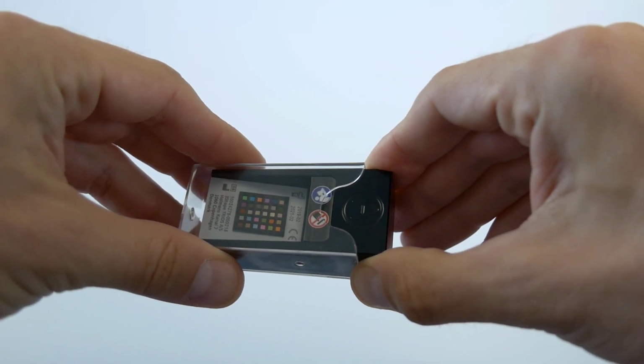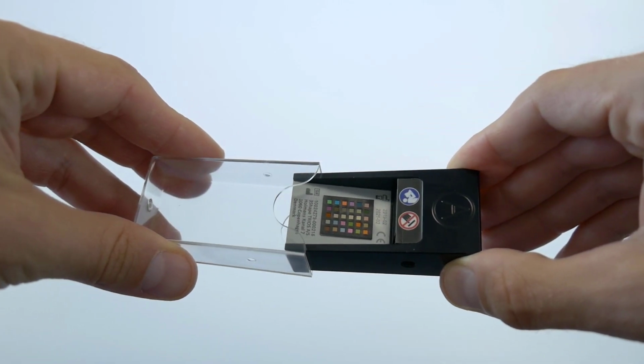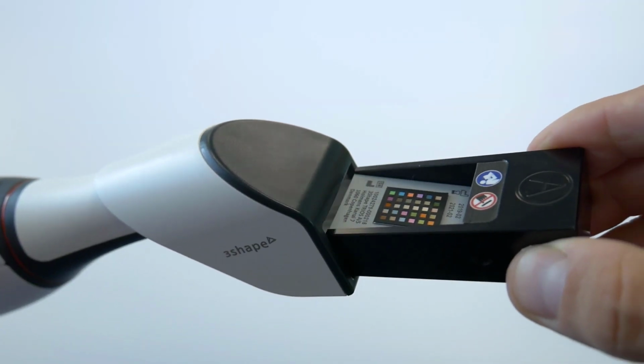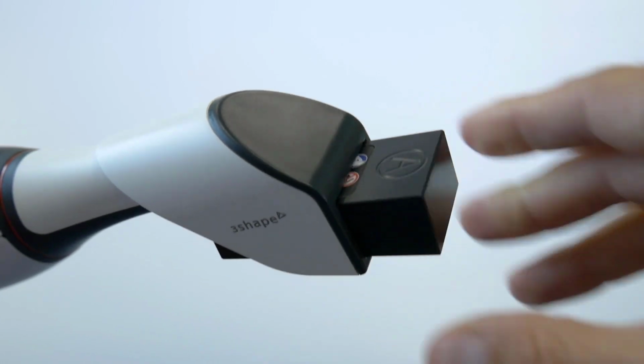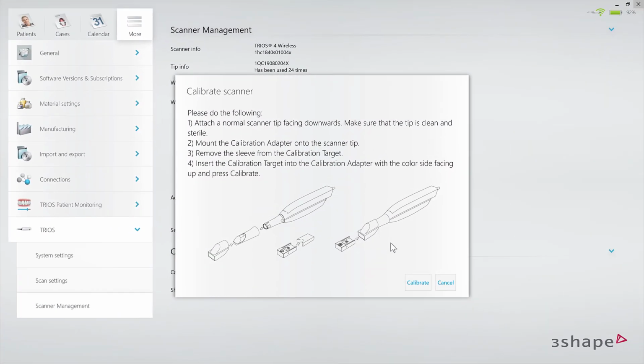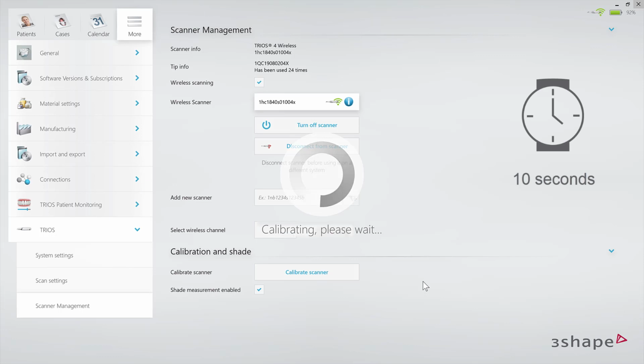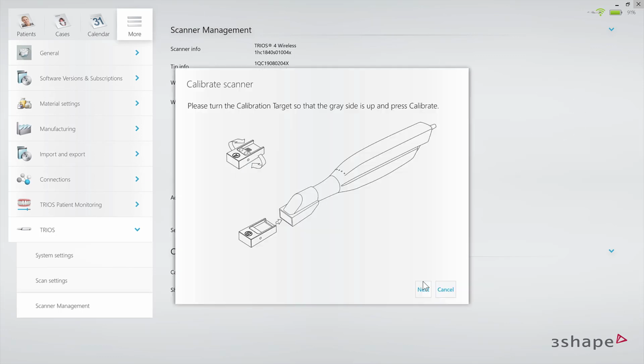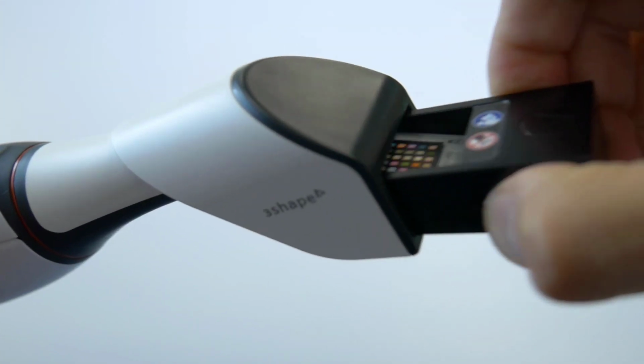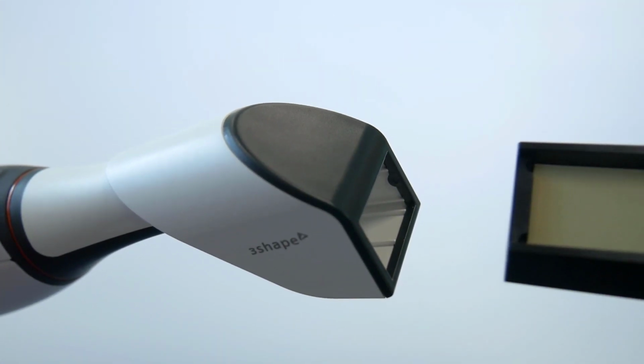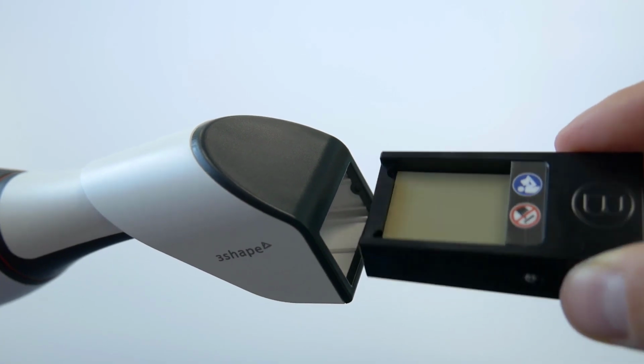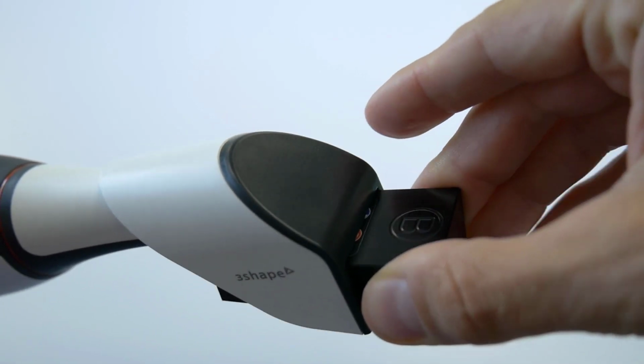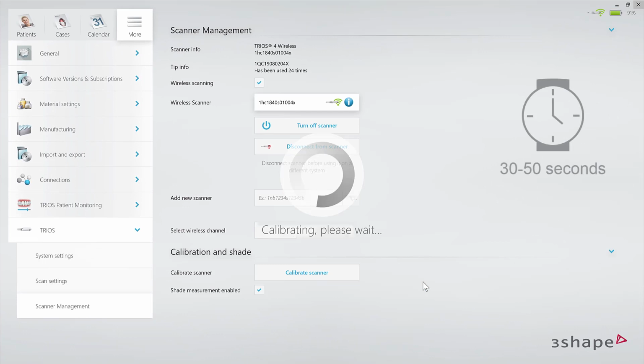Now remove the sleeve from the calibration target. Insert the target with the A side facing up into the adapter and click Calibrate. It will only take up to 10 to 15 seconds. When finished, detach the target, turn it over to face the B side upwards. Upon doing so, reattach it to the calibration adapter and press Next. Wait around 30 to 50 seconds for the calibration and validation to be done.